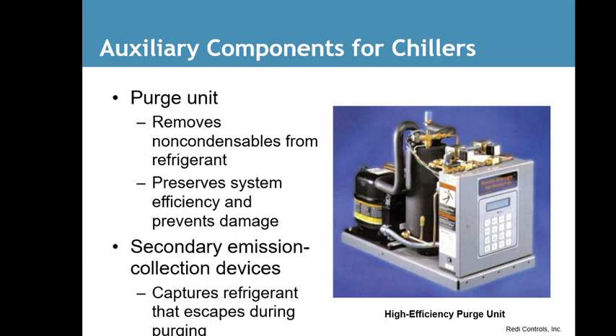Auxiliary components for chillers. A purge unit removes non-condensables from the refrigerant, kind of like a filter dryer. It preserves system efficiency and prevents damage. A secondary emissions collection device captures refrigerant that escapes during purging. These systems, sometimes to keep the pressure down, will purge air out, and purge refrigerant out of the system. And that's what these secondary emission collection devices do. They recover that refrigerant.